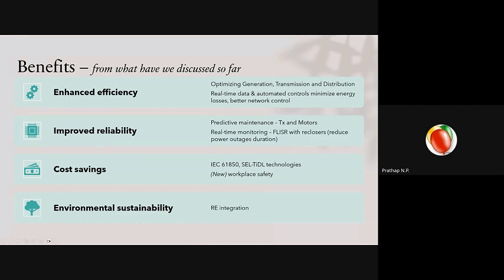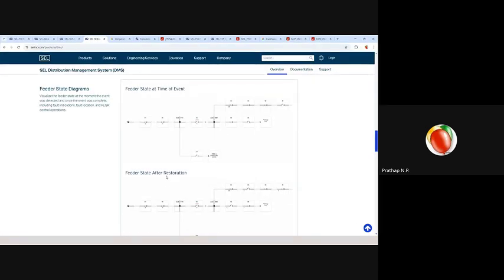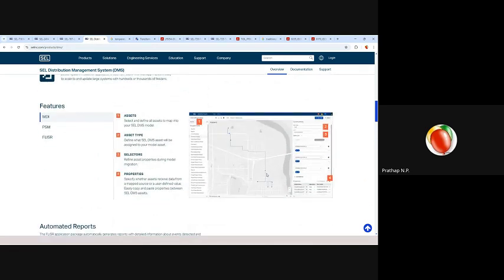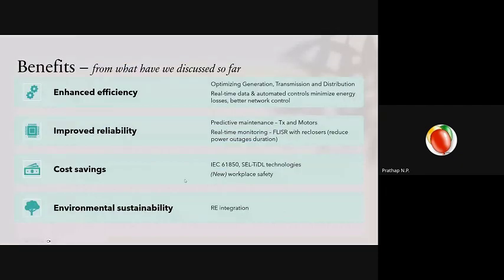So if something trips, you know exactly where to go, instead of what they call walking the line—meaning if it trips somewhere down the line, the utility crew has to drive all the way to find where it tripped. Instead, using this UI, you can see exactly where the recloser opened, go there, and do your maintenance or repair work. That reduces the power outage duration—cost savings.